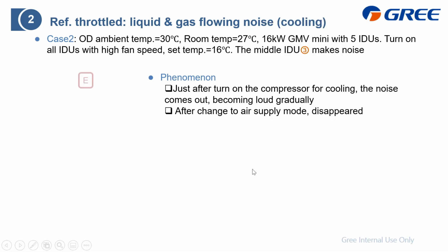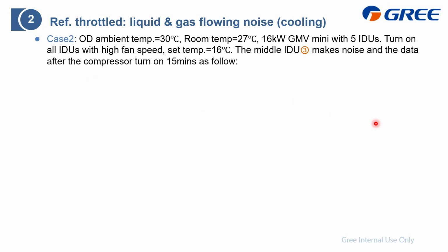Okay, so let's summarize the phenomenon. We just turn on the compressor for cooling, but the noise comes out and becomes loud gradually, and especially when this phone or the microphone is close to the air return, it becomes significant. And also when we change it to air supply mode, this noise disappeared, which means it is the refrigerant flow that makes the noise, right? So with this, it is much easier to analyze and to find the solution. And also we recorded the data for your reference.